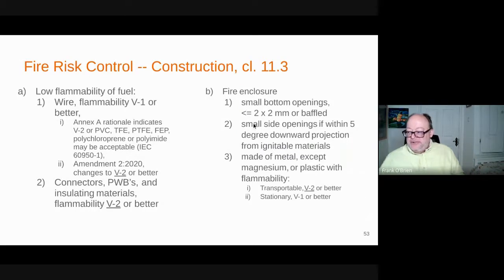All right. And so when we take the construction approach, here's our fuel. Our wire has to be V2 according to the newest amendment. And with the current Amendment 1, there's some Annex A rationale for justifying V2, but it's explicitly required in the amendment. And then connectors and boards have to be V2. So we're taking care of fuel. And then on the enclosure side, we need bottom openings to be very, very small because flammable particles fall. And sometimes we consider the side to be the bottom if you're within 5 degrees. Otherwise, the material of the enclosure is supposed to be metal except magnesium. And if it's plastic, it needs to be V2 if it's transportable or V1 if it's stationary.